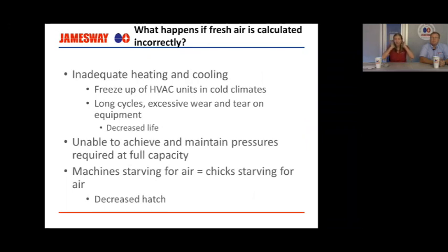So what happens if that fresh air is calculated incorrectly? The first problem is your rooftop unit or your air handler is not big enough, so you're not going to get enough air. But then also there are smaller effects, like you're not going to have enough heating, you're not going to have enough cooling. If it's sized wrong, you could have freeze up of your HVAC units. Your HVAC unit, if it's marginally sized, is going to run for very long cycles. It's going to have excessive wear and tear, so you're going to have a decreased usage life.